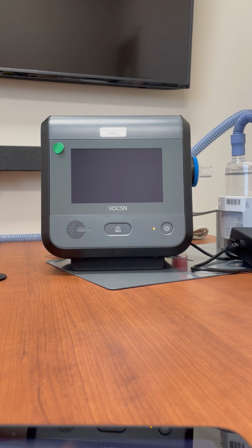and receive therapy. The most common mode that we use for non-invasive therapy is volume targeted pressure support, which is a ventilation mode that delivers a set tidal volume to the patient by adjusting the pressure control target on a breath-to-breath basis. This mode is useful in maintaining a consistent volume delivery in the face of changing patient conditions.